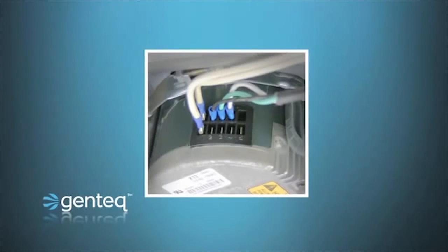Here we see a picture of a package system that is gas only. Therefore, there's only one tap programmed and no need to use any plugs or connectors. Simply use what we call flying leads to each one of the places on the motor that power and communication are required. Since only one tap is programmed and none of those leads will ever need to be moved, this is a perfectly acceptable way to connect the motor. So in the field, you may see an X13 with 2 plugs on it. You may see a high voltage plug with loose wires on the bottom, or you may see loose wires going to the entire motor. It's entirely up to the manufacturer, and there's no right or wrong way to do it.